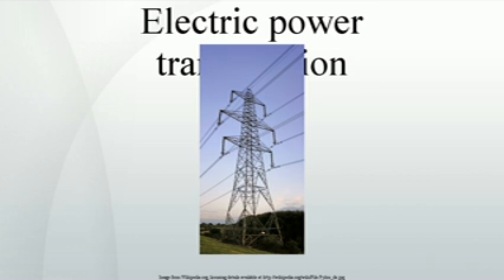In frequency signaling, the generating units match the frequency of the power transmission system. In droop speed control, if the frequency decreases, the power is increased. The drop in line frequency is an indication that the increased load is causing the generators to slow down. Wind turbines, vehicle-to-grid and other distributed storage and generation systems can be connected to the power grid, and interact with it to improve system operation.